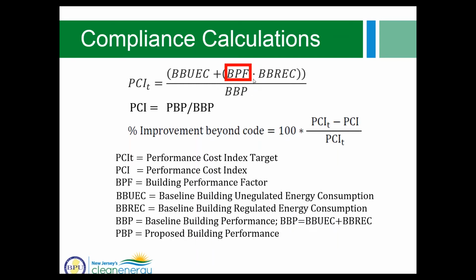So again, building performance factor is the way to adjust stringency of the requirements of 90.1, and the building performance factor required to meet each edition of 90.1 is included in section 4 of the standard. And with each new edition of 90.1, a new set of values is provided. There is a value for each climate zone and building type. And with each new edition of 90.1, the values of BPF go down to reflect increased stringency of the requirements.